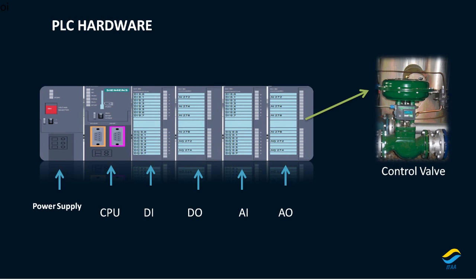We can generate 4 to 20 milliampere or 24 volt based on what type of valve we are using. Like in the case we are using a valve that regulates in between some range of flow, then we will use 4 to 20 milliampere or 0 to 10 volt. And in the case if it is just open and close, then we can just use 24 or 0. So for that we definitely need to have DO, not AO, not analog output card, digital output card.